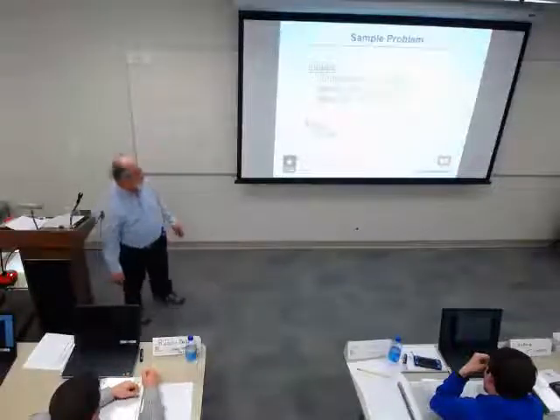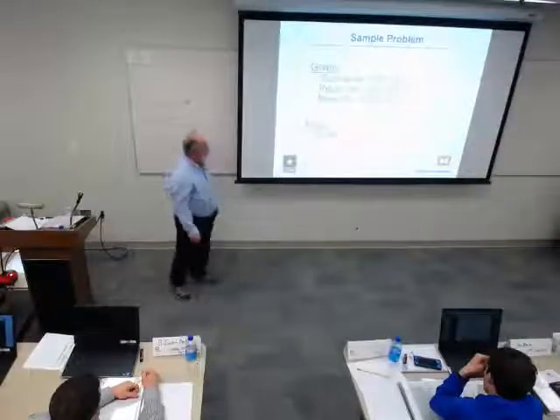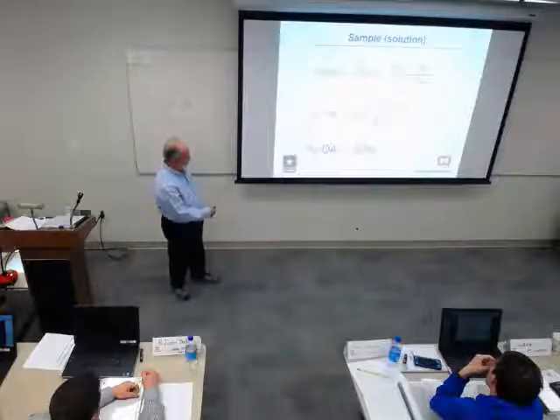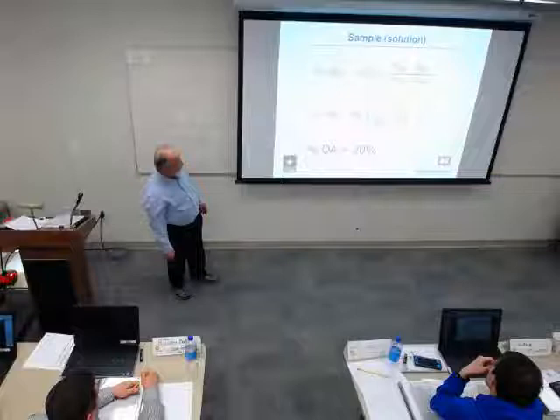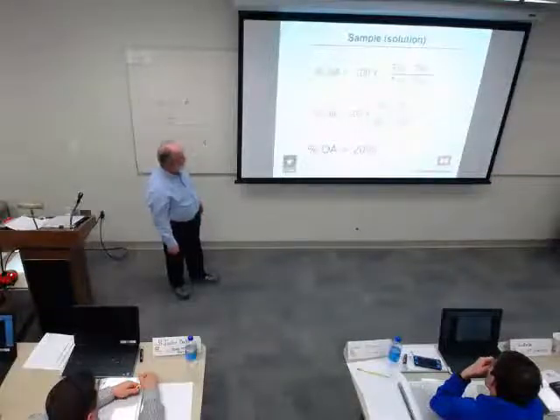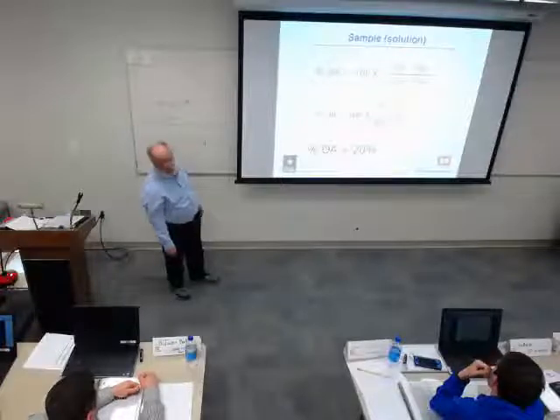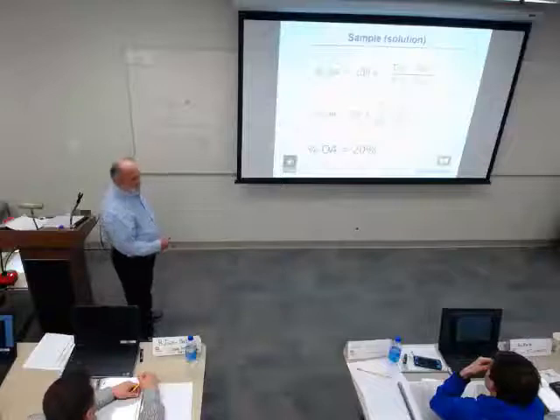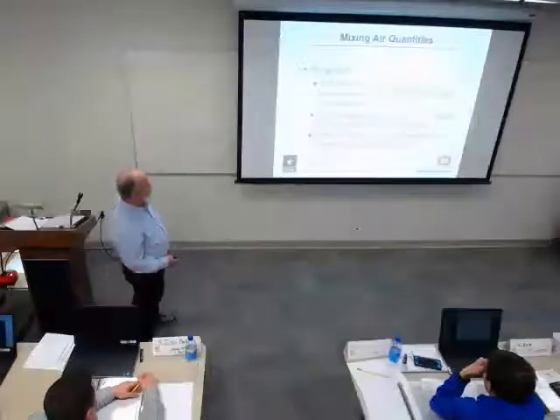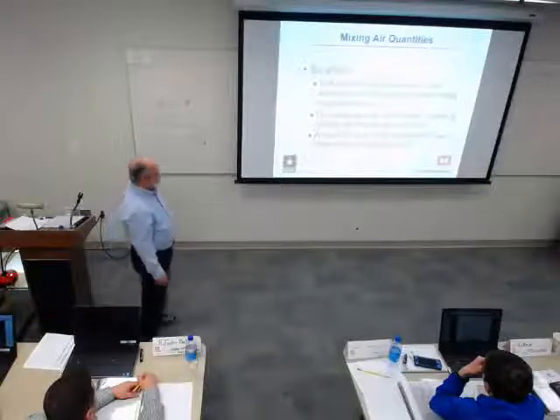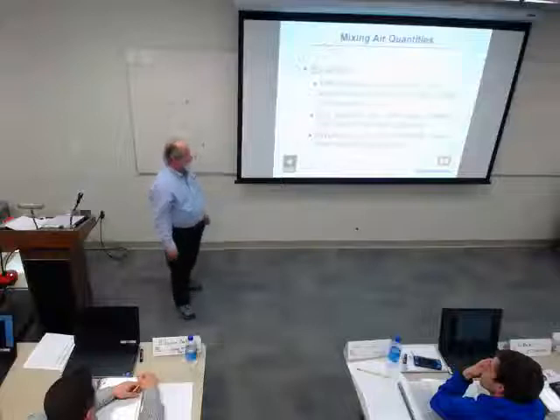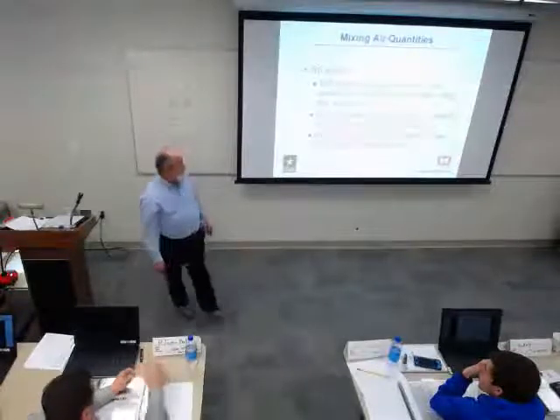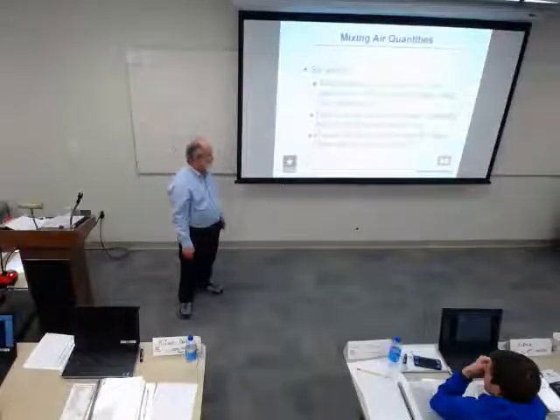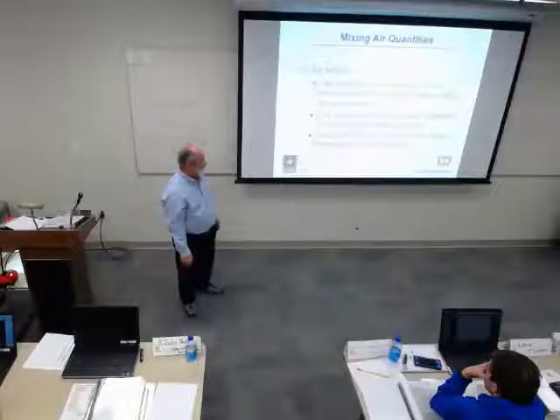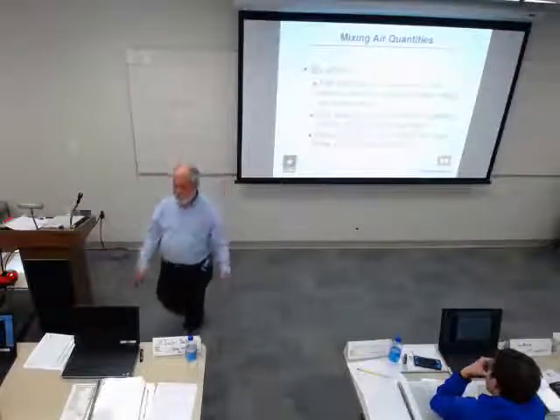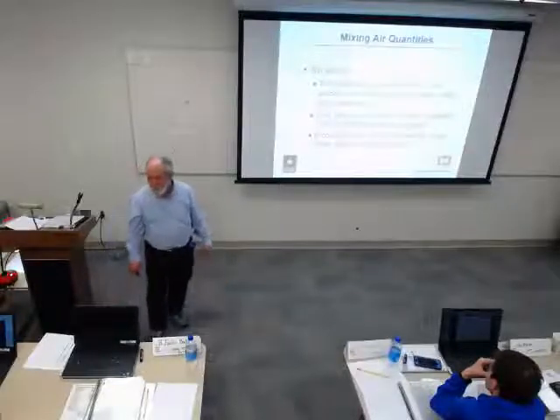So here we have outside air, 95 degrees Fahrenheit, return air 75, mixed air 79, and we're finding the percent of outside air. So we plug our stuff in: 79 minus 75, over 95 minus 75, and we end up with outside air of 20%, which is pretty close to what I found for medical stuff. They usually get 20, 25 for a lot of stuff. All right, so the TAB specialist can determine the percentage of the outside air in the mixed airstream using this relationship. We need to be careful though. We need to use this as a last resort when we're not able to directly measure the outdoor airflow. The amount of outside air is equal to the percent of outside air times the mixed airflow rate, because the mixed airflow rate is the total. Outside air and return air are the pieces.